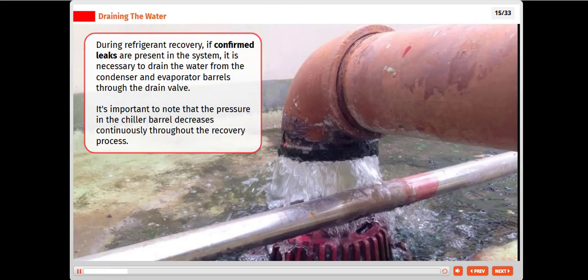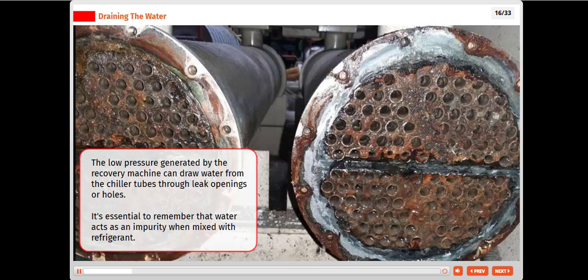During refrigerant recovery, if confirmed leaks are present in the system, it is necessary to drain the water from the condenser and evaporator barrels through the drain valve. It's important to note that the pressure in the chiller barrel decreases continuously throughout the recovery process. The low pressure generated by the recovery machine can draw water from the chiller tubes through leak openings or holes. It's essential to remember that water acts as an impurity when mixed with refrigerant.